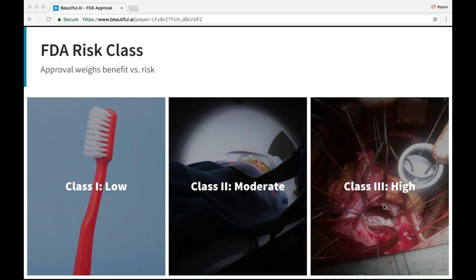In terms of pathways to approval, the thing that I think we should hope for in terms of getting approval for our machine learning technologies is this 510K pathway. It's generally for class 2 risk devices, moderate. It's a little trickier for a class 3 device. And to go through this pathway generally, you need some sort of predicate device. So a prior device that's received approval, generally through pre-market approval, which I'll discuss in a moment. But you need some predicate device that's similar to what you're doing with regards to safety and efficacy.